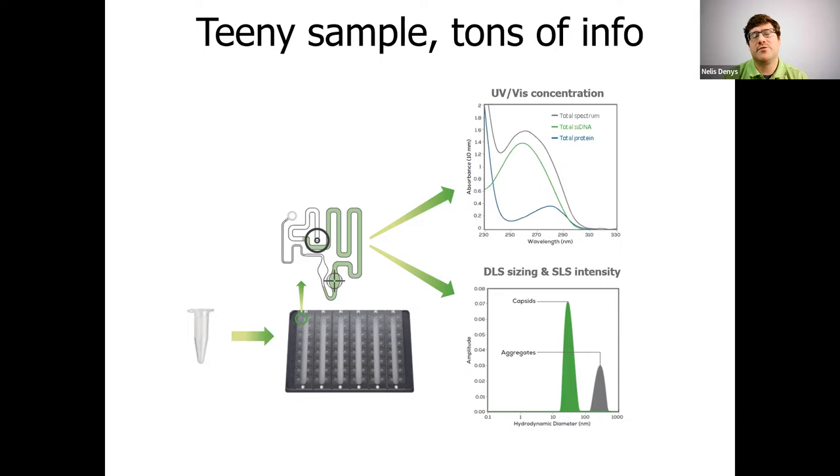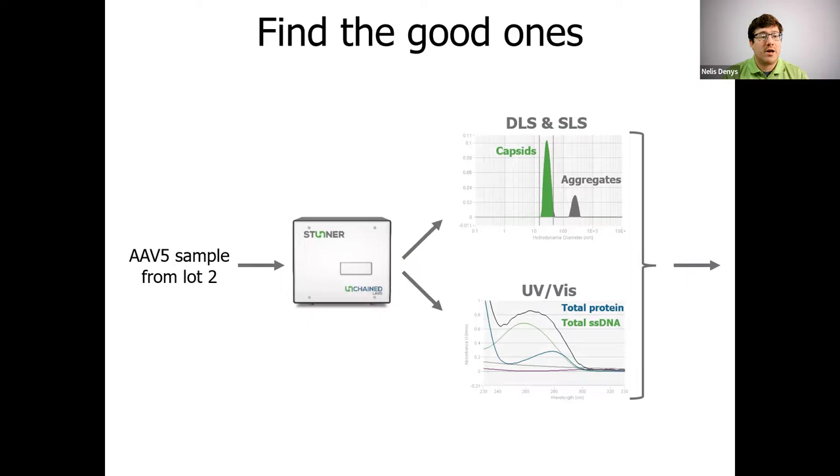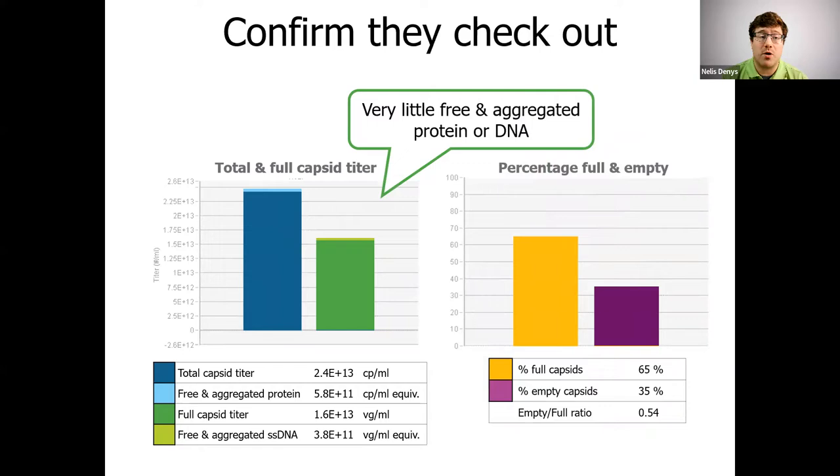Now let's look at some actual samples. Here we ran an AAV5 on Stunner. The DLS already looks pretty good. There's a very small aggregation peak, but most of the signal is coming from the green capsid peak. UV-VIS next to that looks very normal as well. And so when Stunner combines all that data together, it shows you that actually very little free or aggregated protein or DNA exists. So those dark blue and dark green bars go almost all the way to the top. So for this sample specifically, we've confirmed that aggregation is not a big problem. We've gotten total and full titers that show very little extra stuff in there. And we have an empty full ratio as well. That's a pretty good amount of data for just one minute and two microliters.